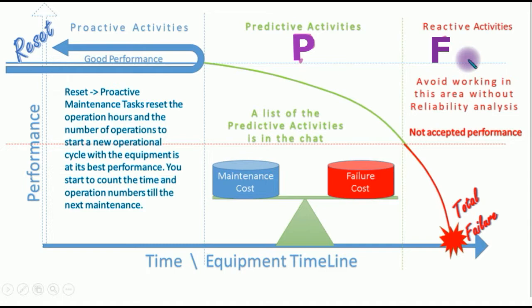And when you reach this range, that's a failure that you cannot retrieve — you need to take some action. So that's the area of the reactive activities. Based on the reliability-centered maintenance, or RCM, without failure you can work in this area, but only for some equipment where the analysis says there is no feasible action that can be done before this area. Otherwise, don't take the risk to work in this area.